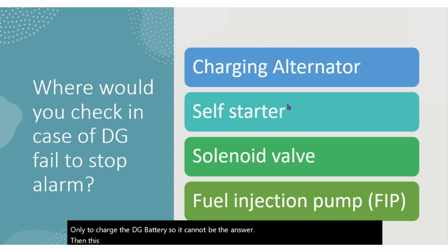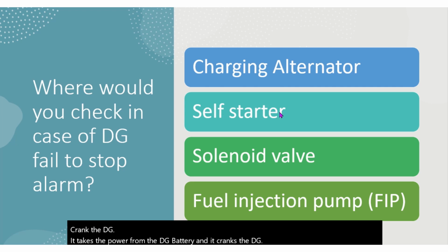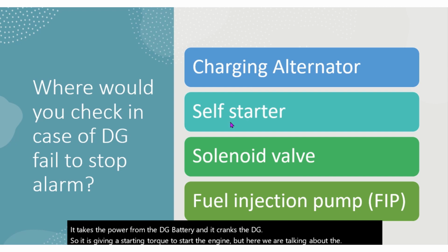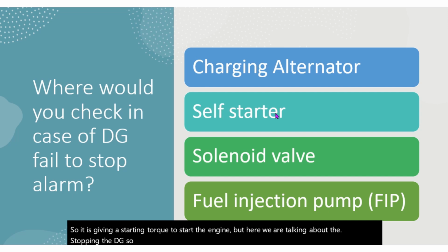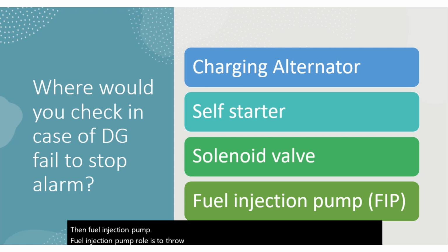The self starter's role is to crank the DG. It takes power from the DG battery and cranks the DG, giving a starting torque to start the engine. But here we are talking about stopping the DG, so the self starter is not the answer. Then the fuel injection pump. Its role is to inject fuel into the combustion chamber as per the requirement. So the fuel injection pump also cannot be the answer.